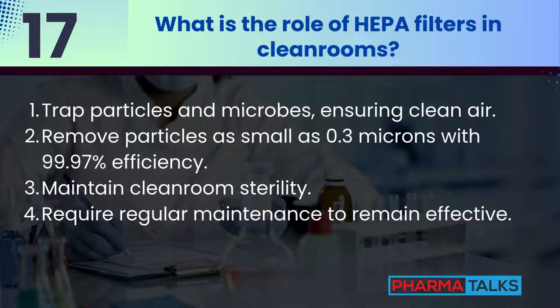What is the role of HEPA filters in clean rooms? HEPA filters trap particles and microbes, ensuring clean air in controlled environments. They can remove particles as small as 0.3 microns with 99.97% efficiency. HEPA filters maintain the sterility of clean rooms, and regular maintenance ensures their effectiveness.